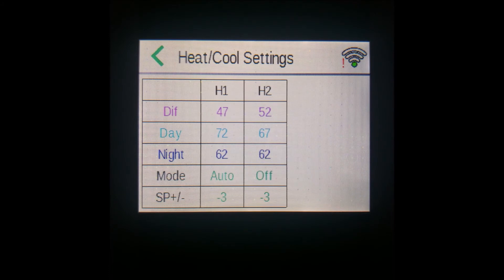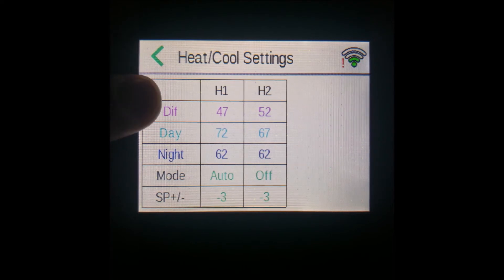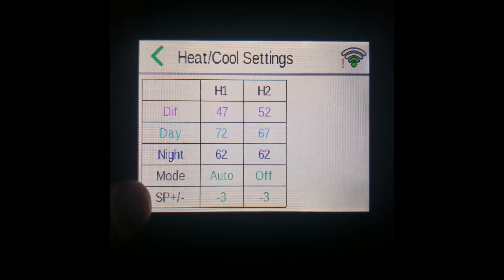On the screen that pops up, you can see a table showing every output's output temperature for each stage of the day. With your settings on the side here — diff, day, night, mode, and set point plus or minus the offset — and then you have the outputs on the top: heat one and heat two.